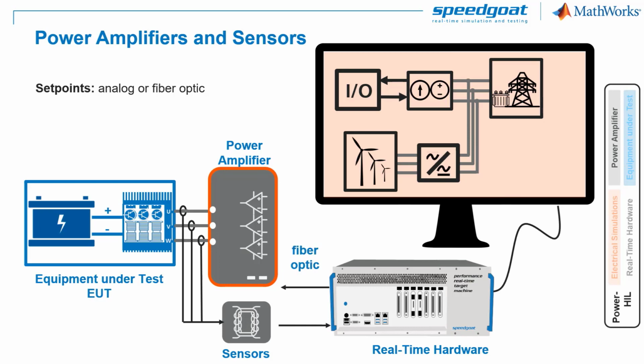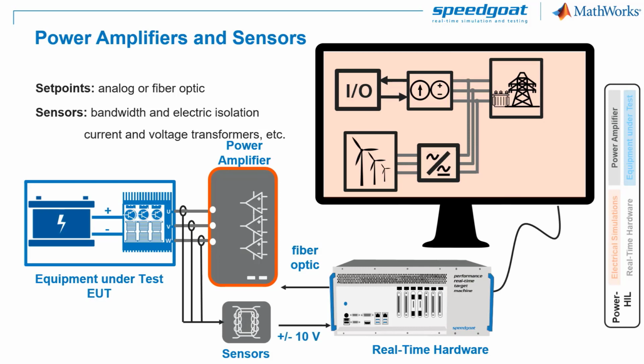Sensors for voltage and current are meant to provide outputs at extra low voltage for real-time hardware. Key considerations include electric isolation and a high bandwidth, at least as high as the simulation closed-loop bandwidth. Voltage and current transducers would typically require to output voltages in the range of plus minus 10 volts to interface with the real-time hardware, and they can also be available with the fiber optic link. Power amplifiers also tend to include sensor signals with an interface to the real-time hardware.